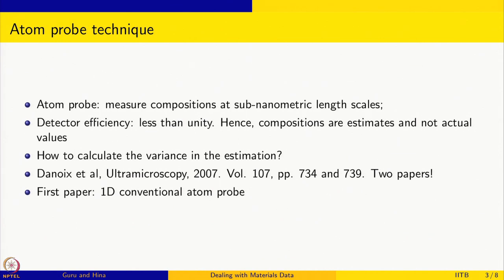The atom probe technique is a technique to measure compositions at sub-nanometric length scales. The composition measurement depends on detector efficiency, and detector efficiency is less than 1. That means if there are 10 atoms pulled out from your sample and all 10 fall on the detector, the detector does not recognize all 10 of them. It detects only some fraction of the atoms that actually reach the detector, because of which the compositions we measure are actually estimates.